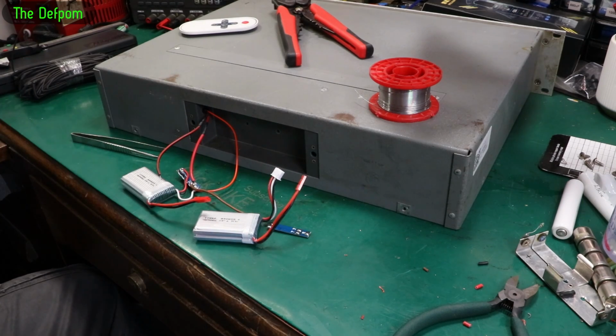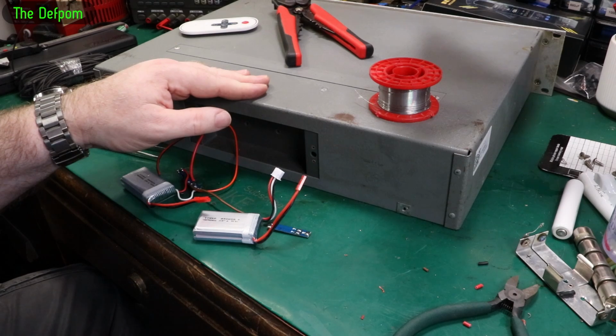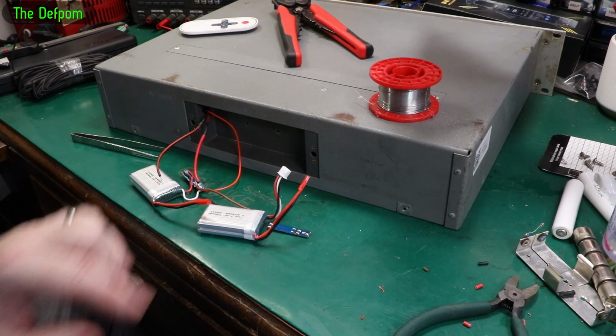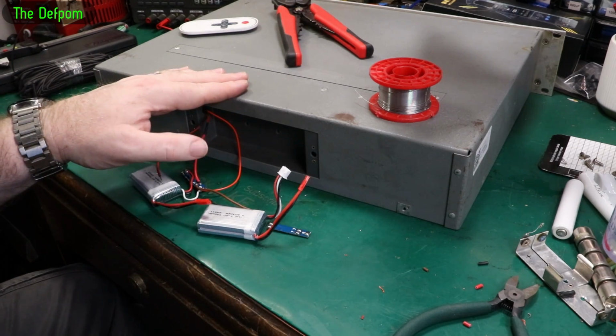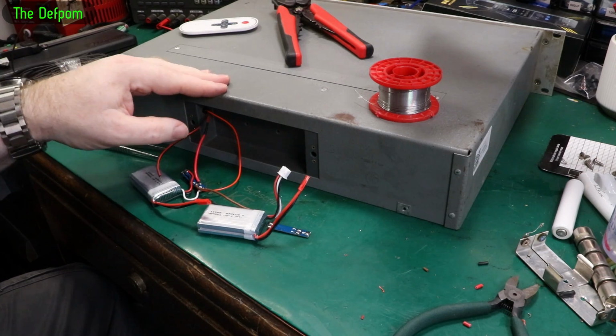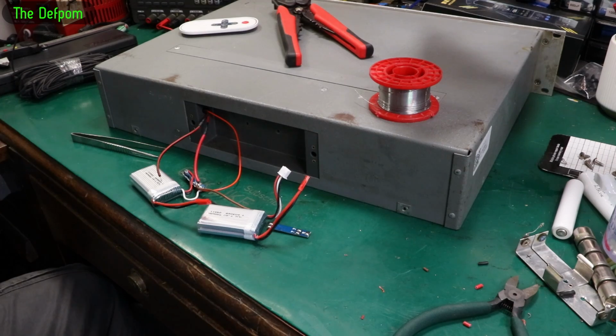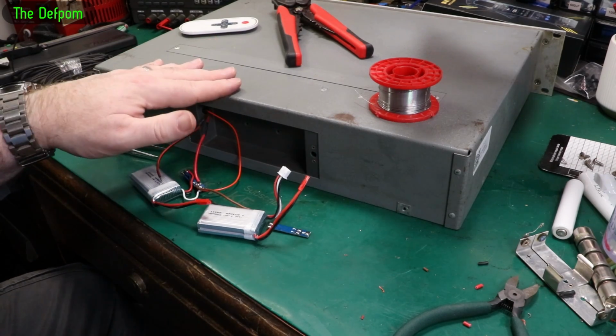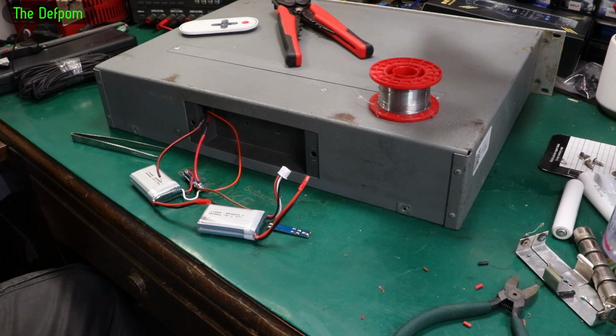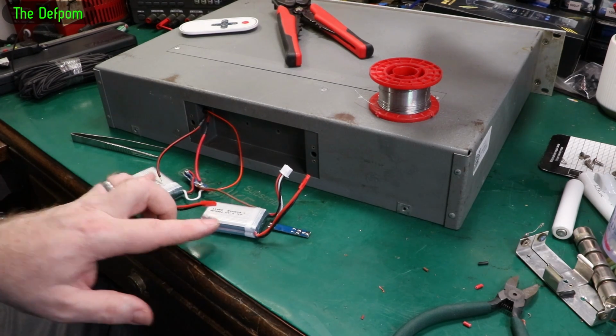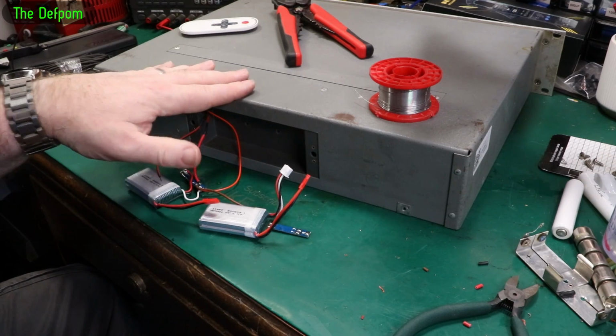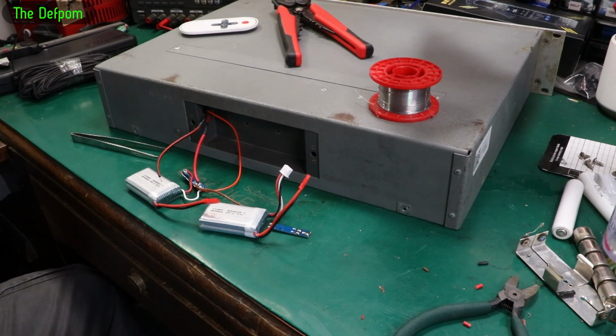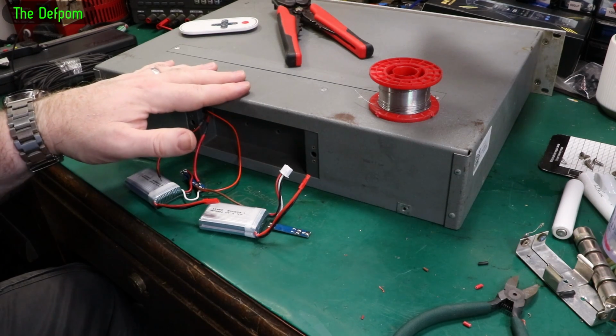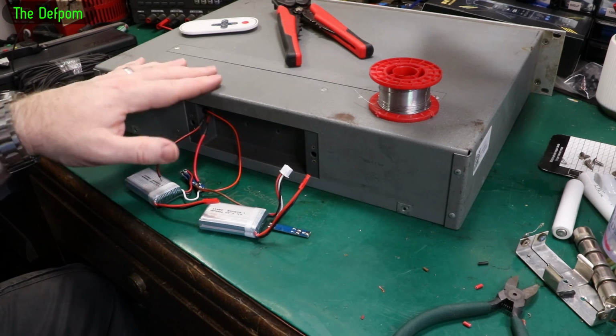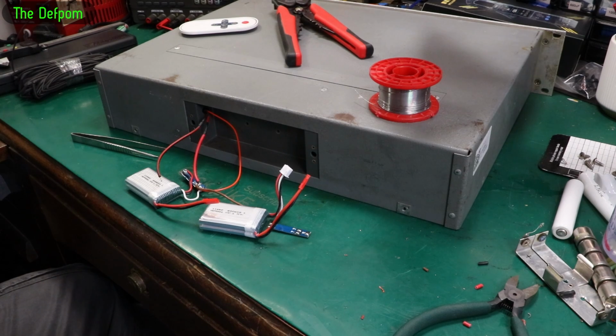I mean, that even may be what I do, because this isn't going to get used very often, and these only do one function. They provide protection. It's a protection relay inside this thing. So if you overload the input with too much voltage, then it will disconnect the input and protect itself, so not damaging the resistors inside it, that sort of stuff. So that's a really nice feature. And obviously you want to make sure that's working, which is all these batteries do. All they do is protect this unit from an over voltage. That's it. So technically, if you're really careful, you could run it without the batteries at all, and it'll be fine as long as you never overload the input. But I'm not going to take that risk because I'm not that good. I will probably get it wrong at some point.